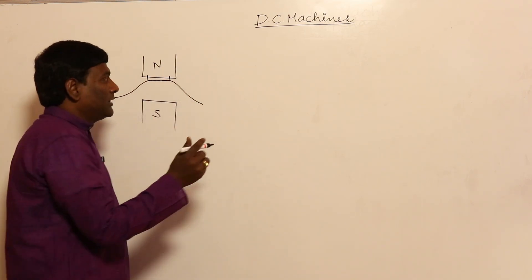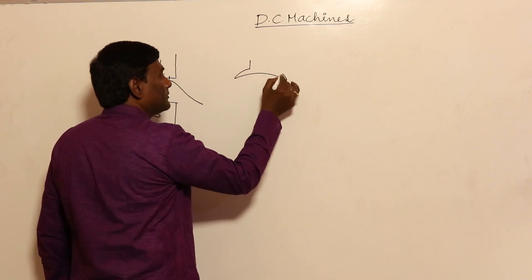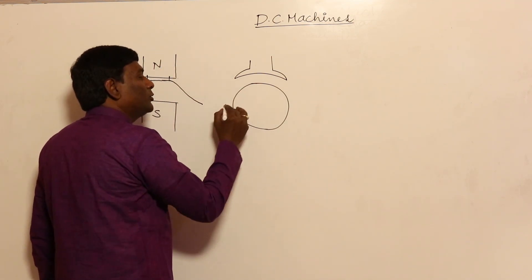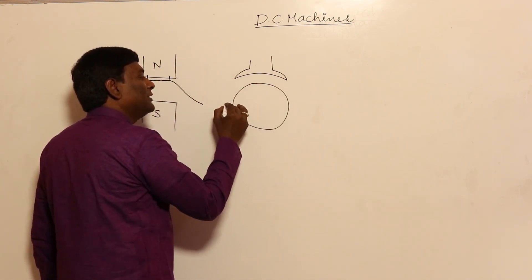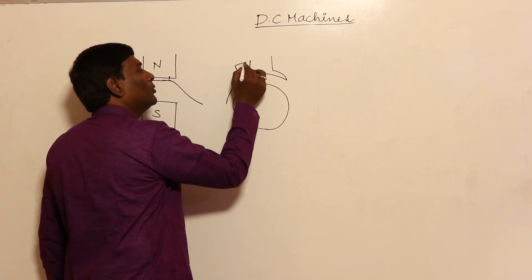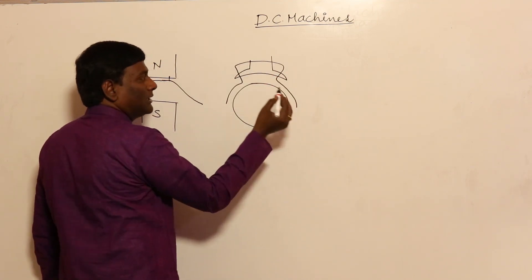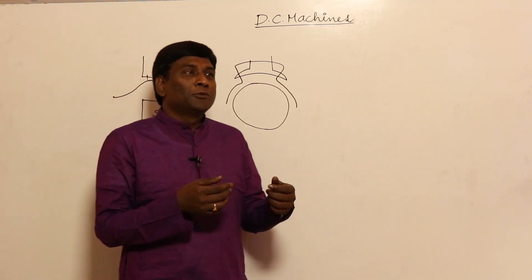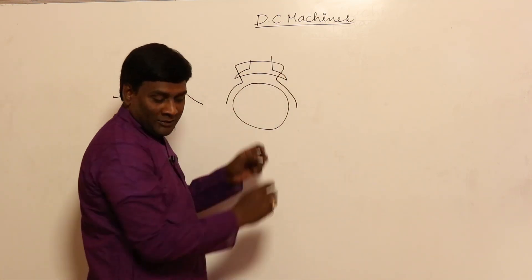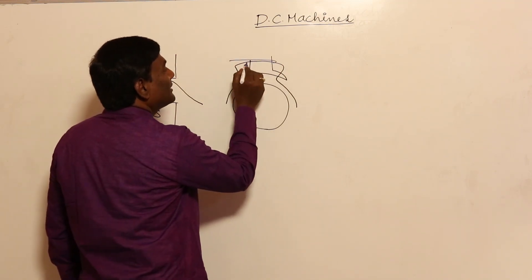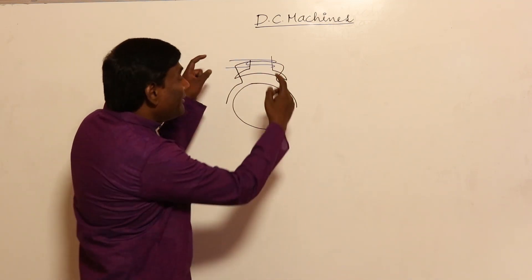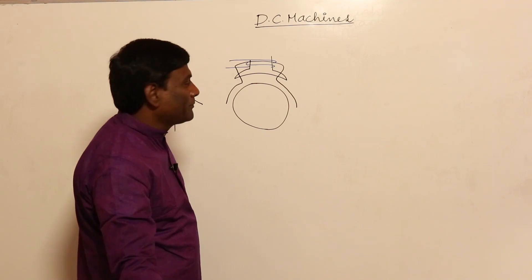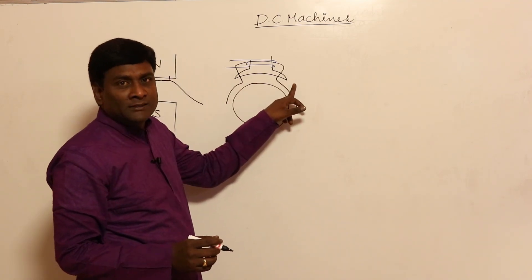Now, if I can increase the pole shoe area — if I think of the rotor like this — from here to here, the flux density is going to be almost flat-top and constant, and after that it will drop. Because pole shoe area is more. Actually, some textbooks say that the pole shoe area should be more to hold the field windings so they don't fall — which is actually a funny reason.